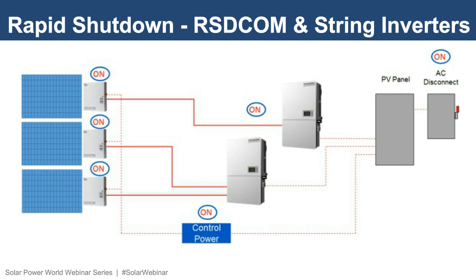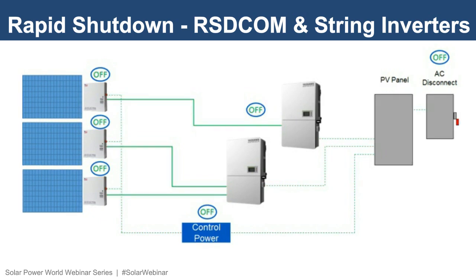With the system disconnect closed, as shown on this slide, the inverters, the rapid shutdown combiners, and the PV output conductors are all energized and operational as conditions permit. Now, in the event first responders need to initiate a rapid shutdown of the PV array, the system disconnect is opened. The inverters will lose their AC source and disconnect immediately.